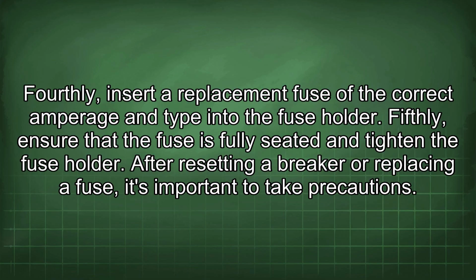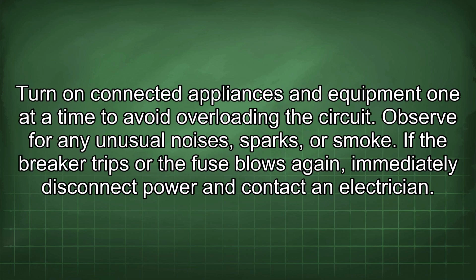After resetting a breaker or replacing a fuse, it's important to take precautions. Turn on connected appliances and equipment one at a time to avoid overloading the circuit. Observe for any unusual noises, sparks, or smoke. If the breaker trips or the fuse blows again, immediately disconnect power and contact an electrician.